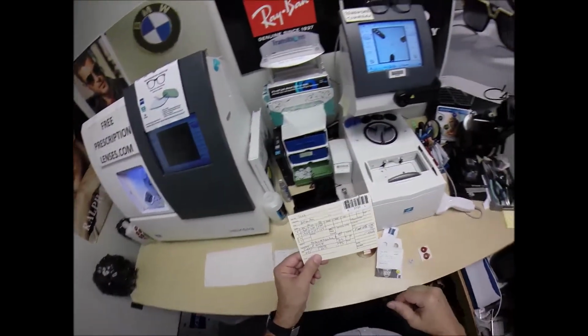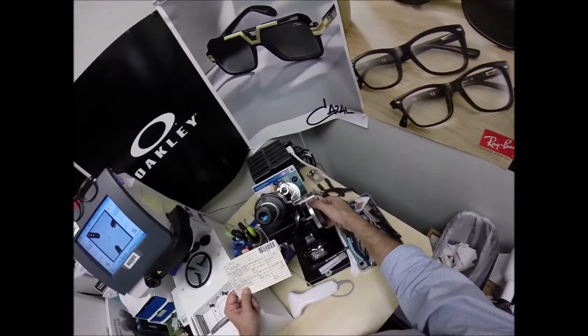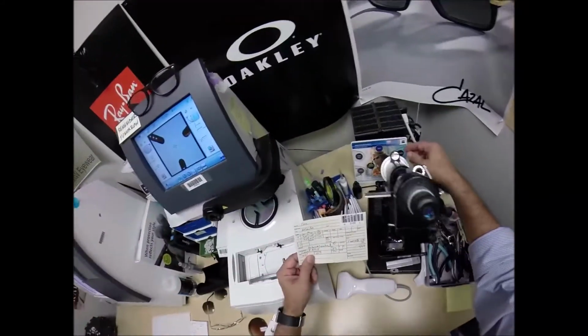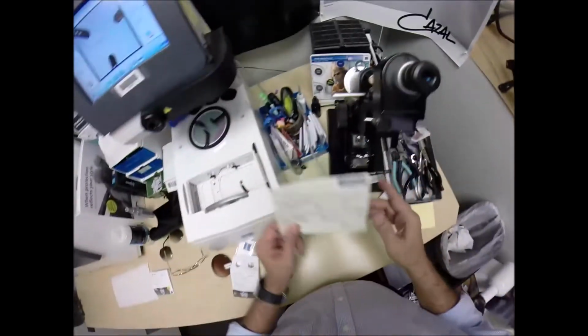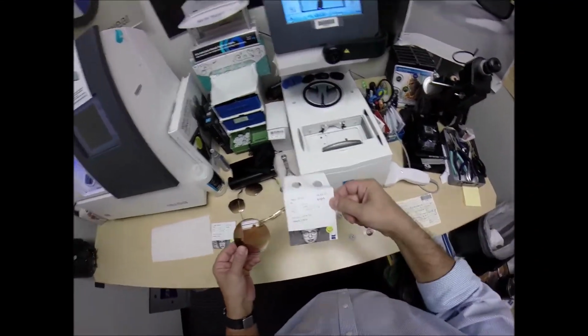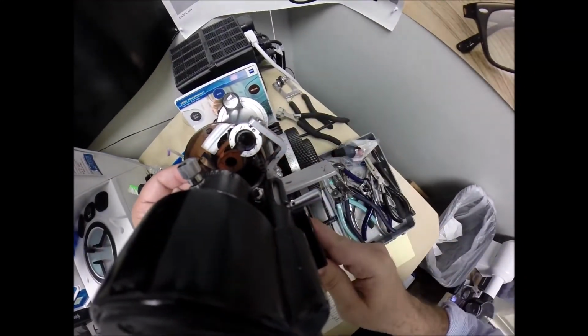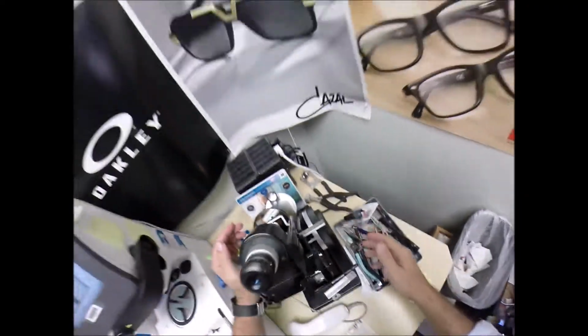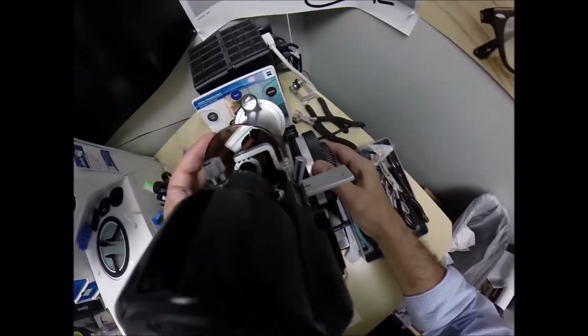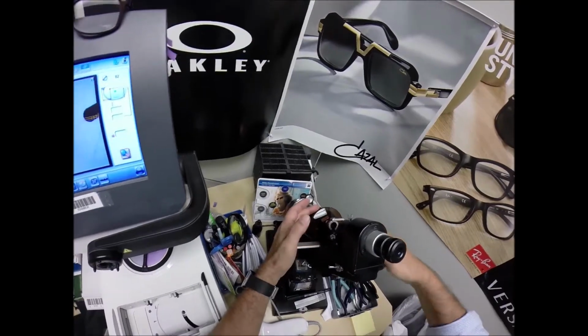So let's go ahead and get your lenses prepped. I'm going to turn the power drum to -3. Actually, let me make sure everything's on 0. Okay, we're good. Put on -3. Turn the axis wheel to 30. And this one was marked the right lens from Zeiss, so I'm going to put that in there. Rotate until the spherical component comes into view first. I'm going to go ahead and check your astigmatism correction. We are good to go. I'm going to put 3 dots on your lenses.